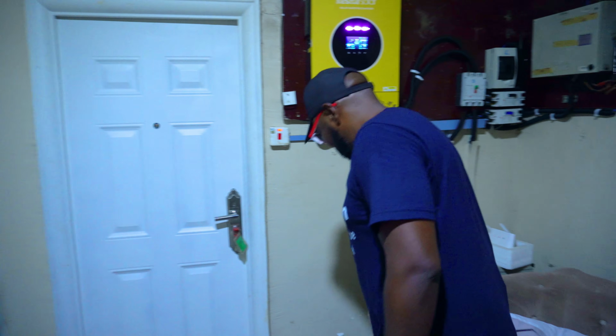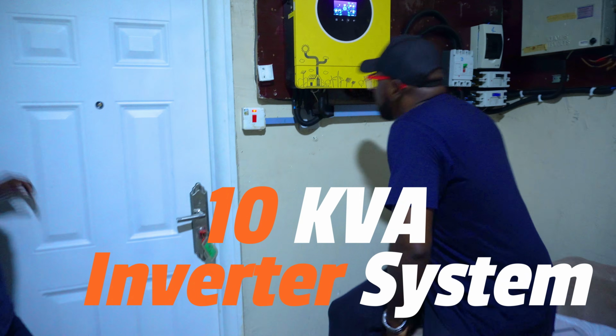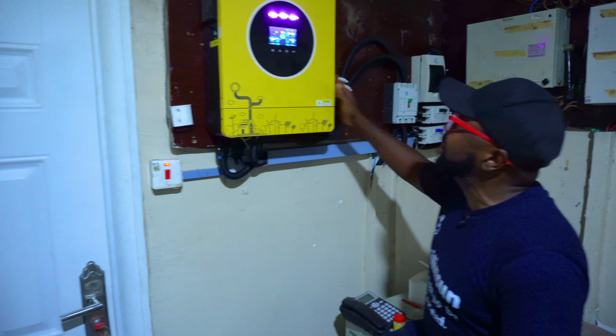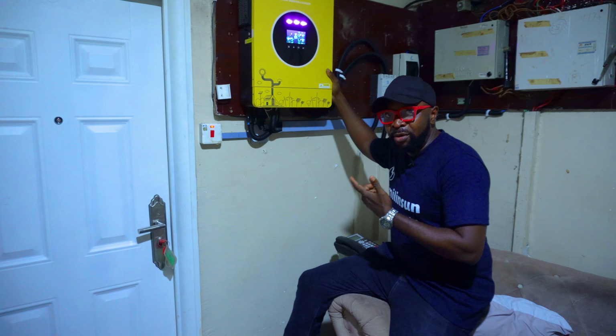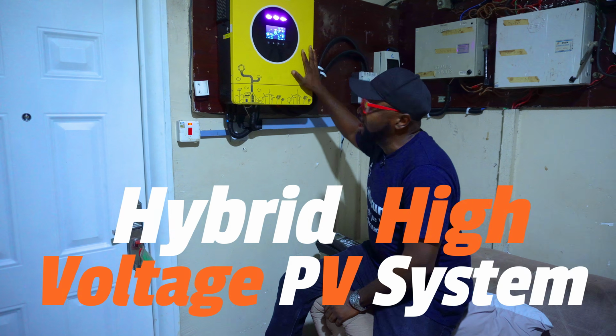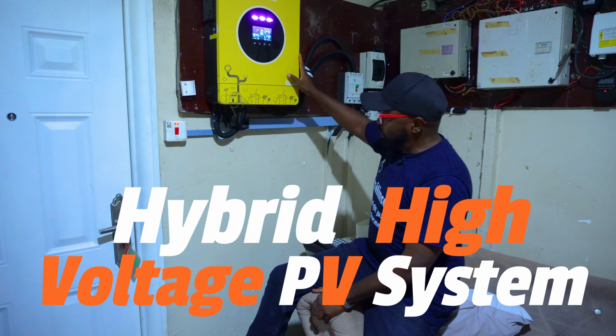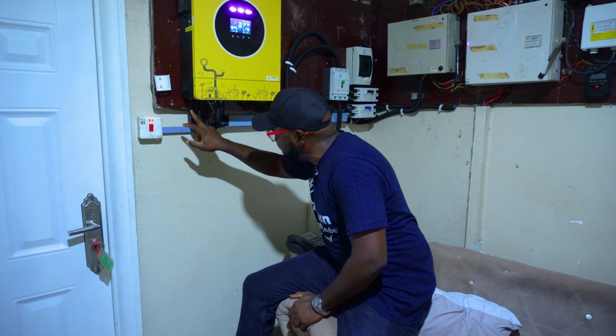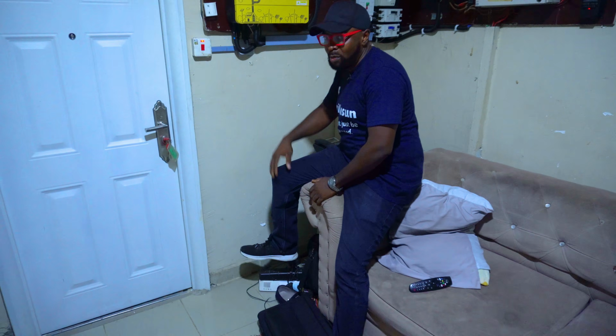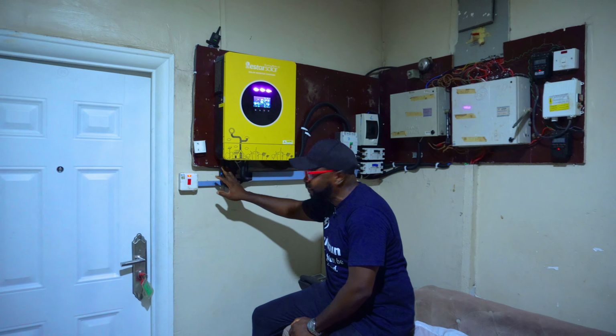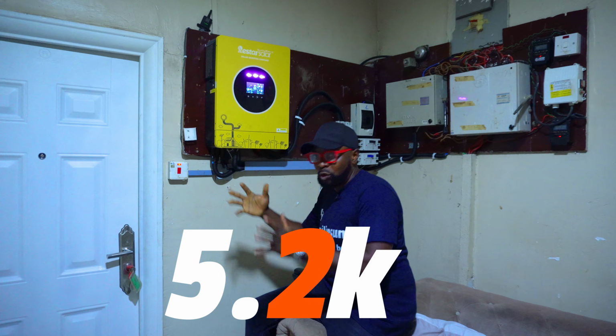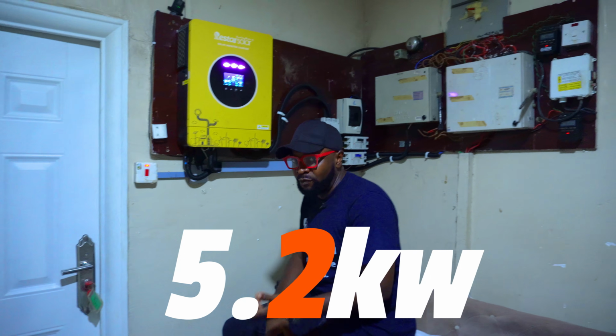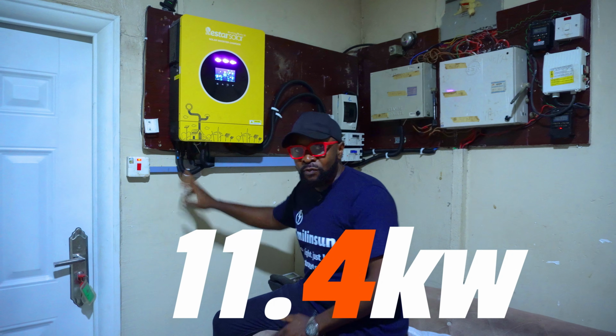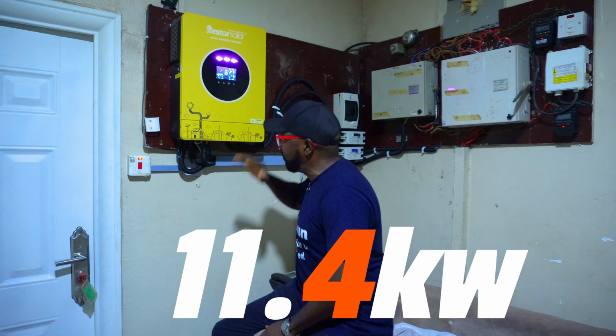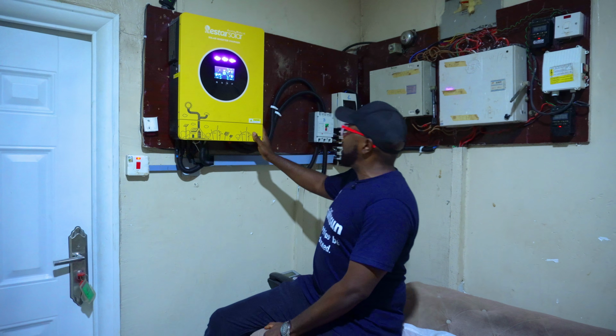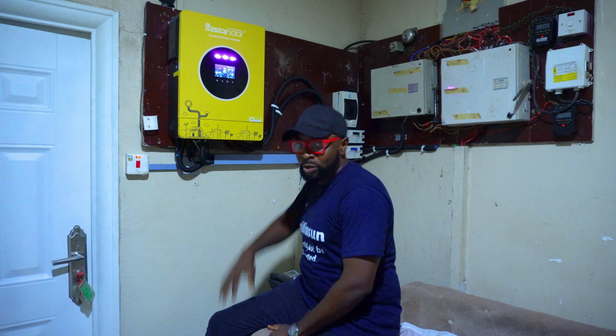I'm kind of familiar with this particular system. It's a 10 kVA system, a hybrid, and also a high voltage PV system. It has two PV inputs, as you can see here. Each of the inputs, if my memory serves me right, is around 5,700 watts each. So cumulatively, it's around 11,400 watts, and that's the max PV wattage you can put into this system. It's pretty good, a fairly good system that doesn't give problems.